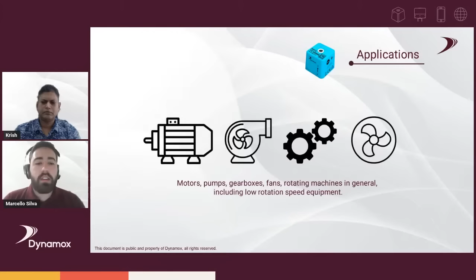Because it's going to lower the frequency down a bit, so you can see down to 2.5 kilohertz. In terms of the HF plus, this is our general application sensor, for motors, pumps, gearboxes, fans, everything, including low rotation speed equipment. As this waveform goes up to almost 3 minutes of collection, you can use that for low speed applications like reclaimers and mills, and also for high speed machines. If you're talking about more than 5,000 rpm for a high speed machine, you could use it because you have a larger frequency range up to 13K, and you'll be able to monitor that.